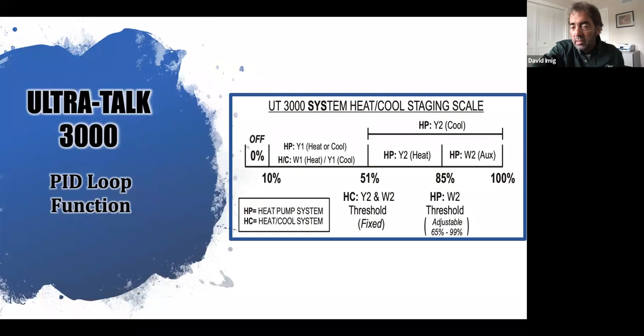In 22 seconds, I'm going to take a reading and see if, let's say this is the heating target I'm looking for, I'm at 142. If I'm not at 142, I go up to 37%. 22 seconds later, I go up to 38. 22 seconds later to 39, and so on.